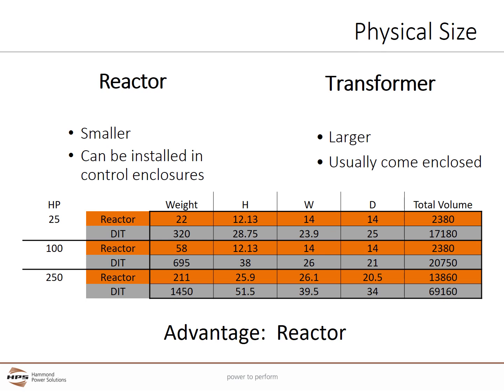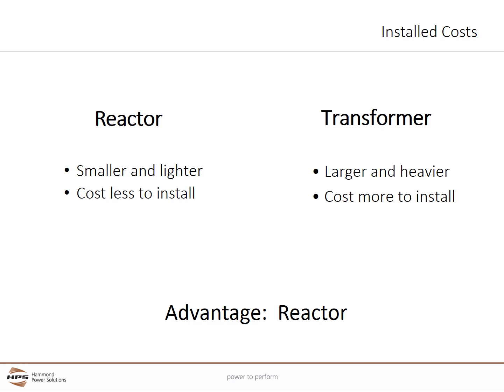Physical size. As you can see by the chart, reactors are much smaller and lighter than the equivalent DIT. Line reactors can often be installed in a control enclosure, which can further protect them and allow easier wiring to the VFDs. Reactors, even while enclosed, have a large size and weight advantage over transformers. Installed cost. If reactors are smaller and lighter than transformers, they must use much less material and cost much less than the equivalent transformer. Reactors' small size and weight often means they are also easier and less expensive to install, giving reactors an advantage in overall installed cost.